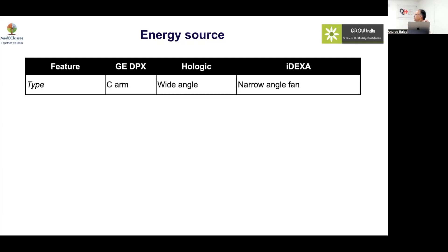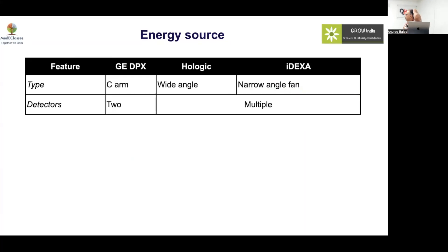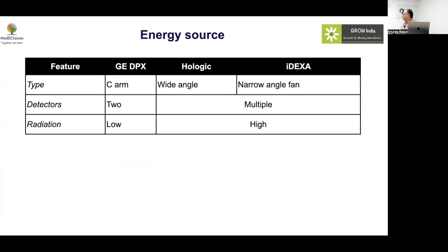The GE DPX uses a C-arm configuration, while the Hologic uses a wide beam versus narrow beam design with two detectors compared to multiple detectors. Radiation exposure is more for Hologic and iDXA but still much lower compared to a standard X-ray.